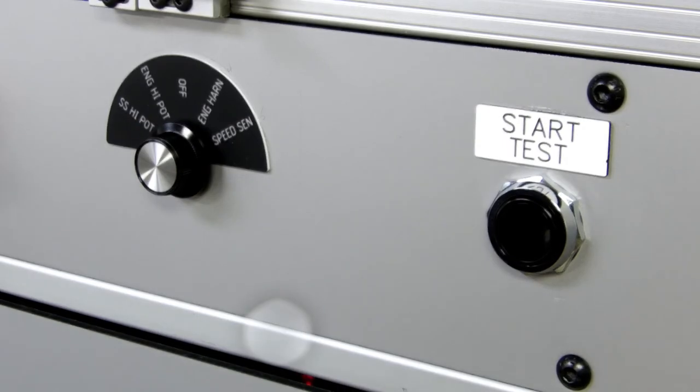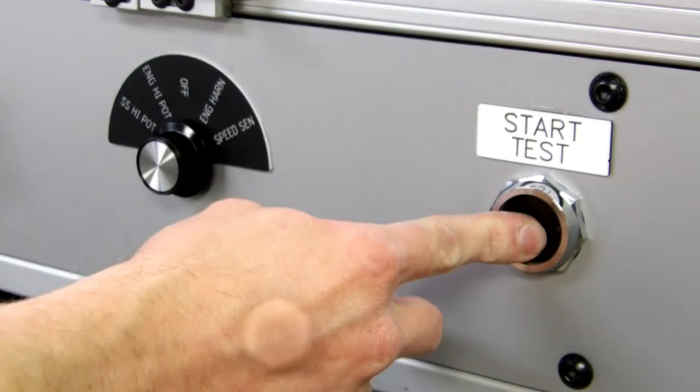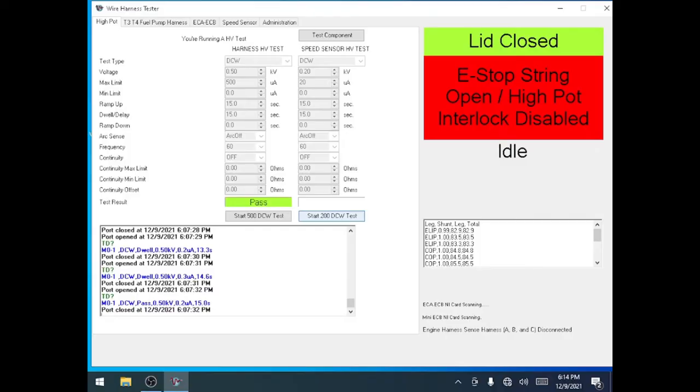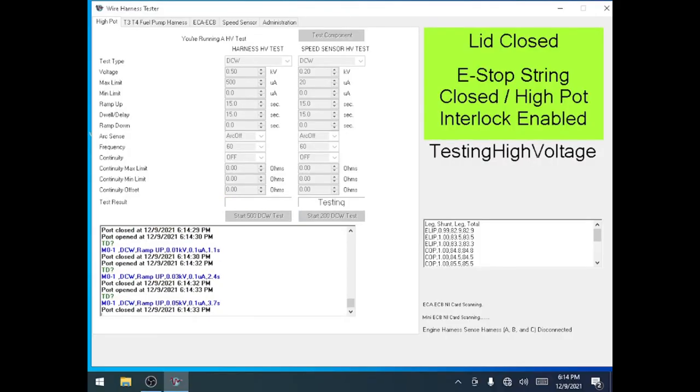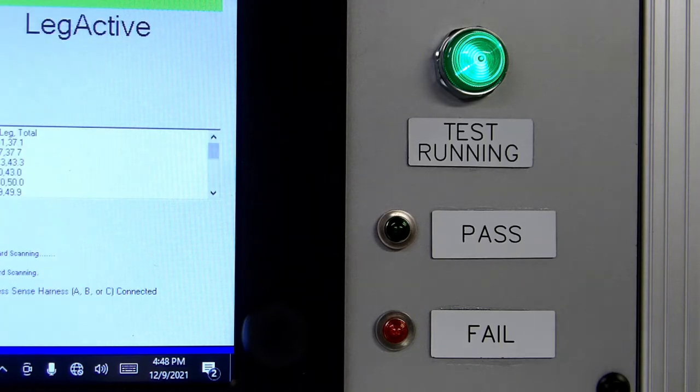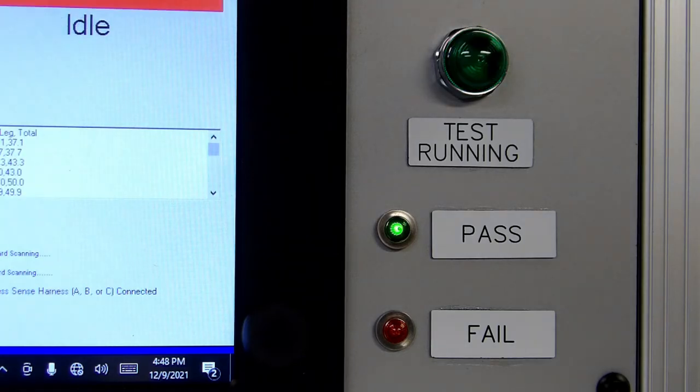Press the start button beside the selector switch to start the HIPOT test. The high voltage indicator will flash on the front of the operator console while the test is running. Once the test is complete, the high voltage flasher will go out and the pass fail indicator will light.